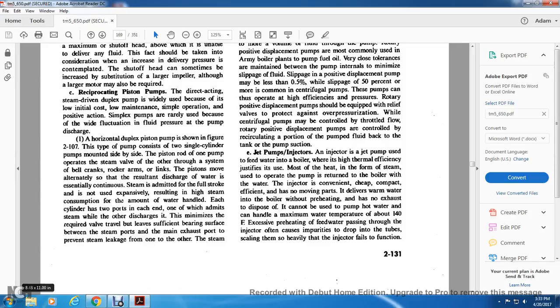Reciprocating piston pump. The direct action steam driven duplex pump is widely used because of its low initial cost, low maintenance, simple operation, and positive action. Simplex pumps are rarely used because of the wide fluctuation of fluid pressure in the discharge. A horizontal duplex piston pump is shown in Figure 2-107.